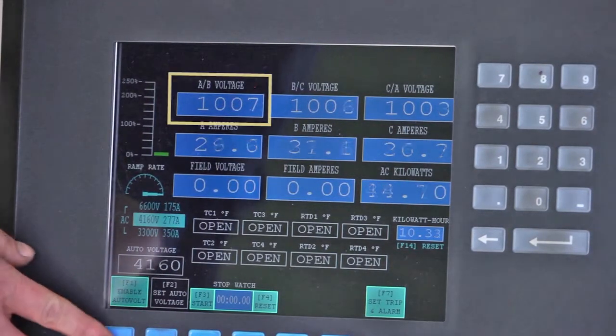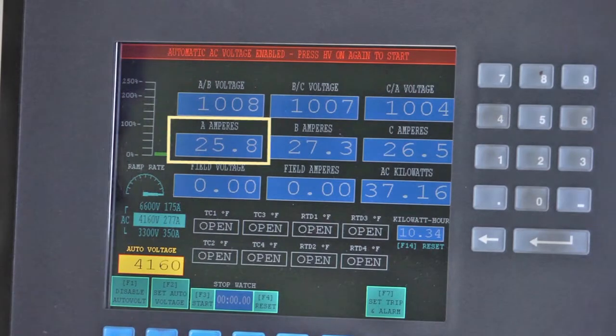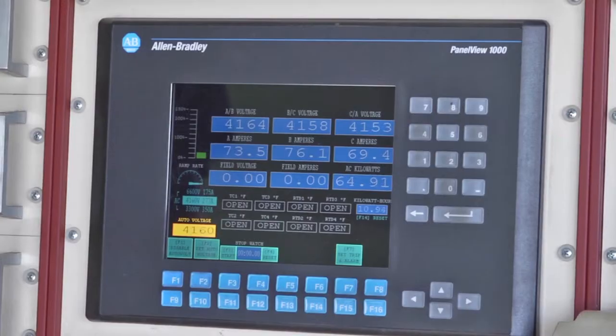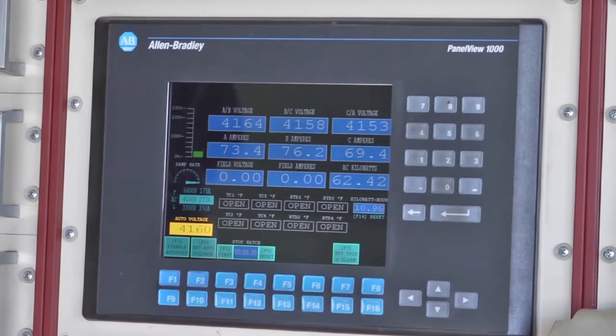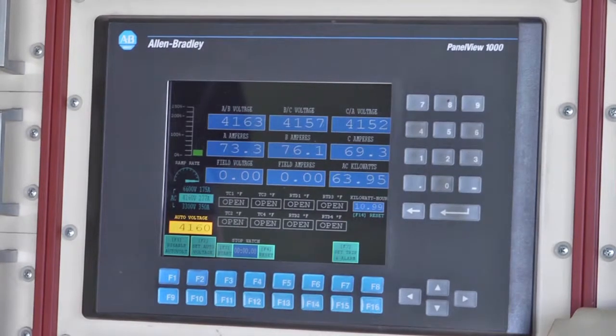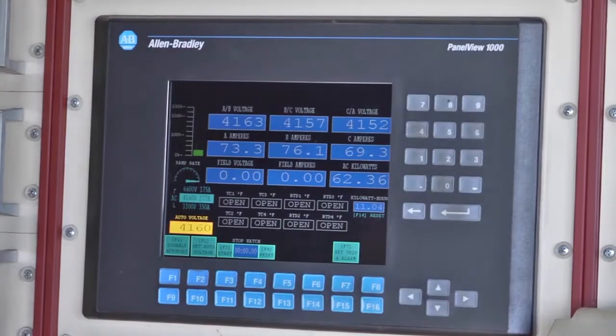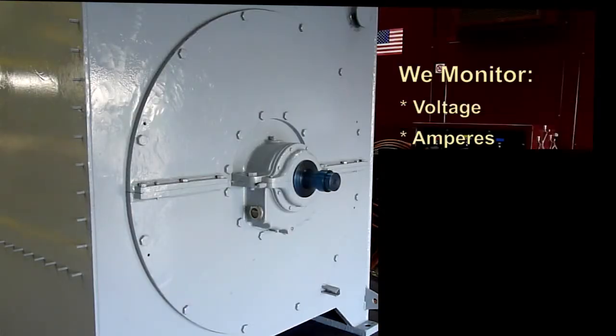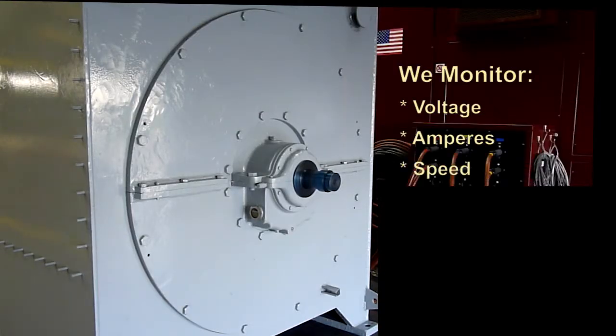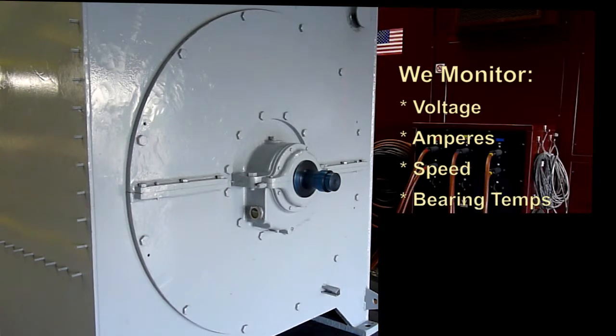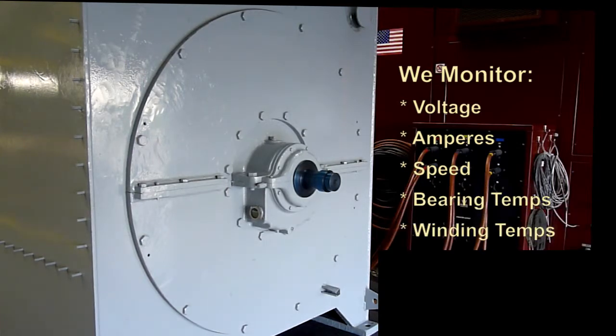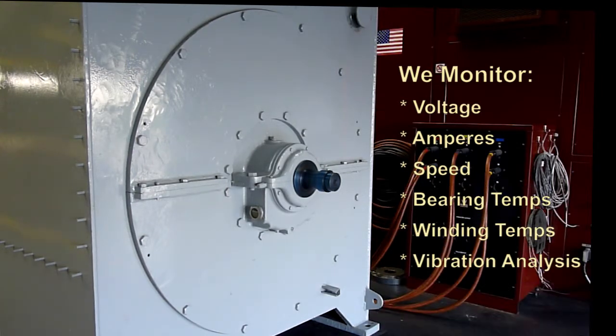The voltage is being applied on the top. The second is the current. And once it's up to speed, the computer will now read the voltage, the amperes, and the speed, the bearing temperatures, winding temperatures, and also the vibration analysis all in the computer program.